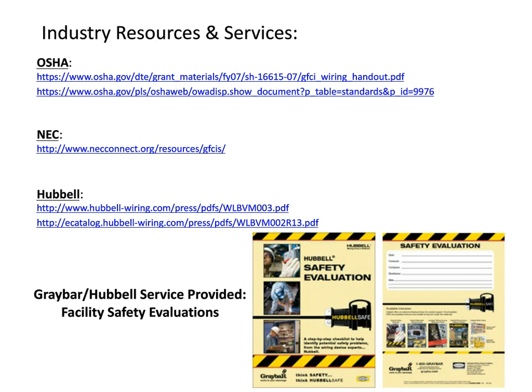So if you're a safety person in your facility and you want to improve the safety, does it make sense for you to change out all your ground fault receptacles and go to a self-testing product? Yes, it makes sense, and it will make your facility safer. Is it a requirement? No, it's not a requirement. The UL mandate strictly applies to the manufacturing of the device. So from an end user standpoint or from a contractor standpoint, you're perfectly okay to install the existing product that exists in the marketplace. You don't have to change out every GFI in your home. But if you want to improve the safety of your own family, then yes, it is a good idea to install one of these new UL 2015 self-testing ground faults. And with that, again, Mindy, I'll let you take it over.